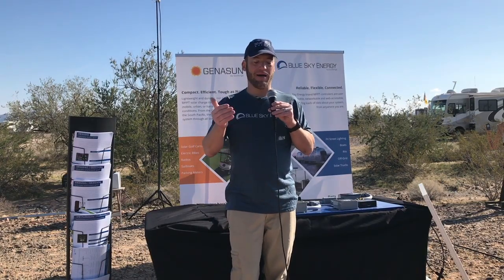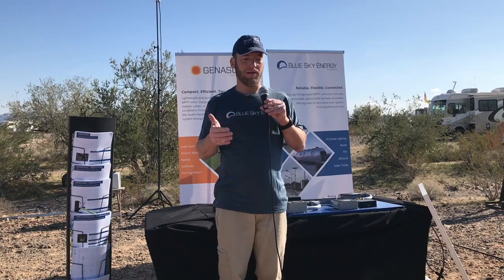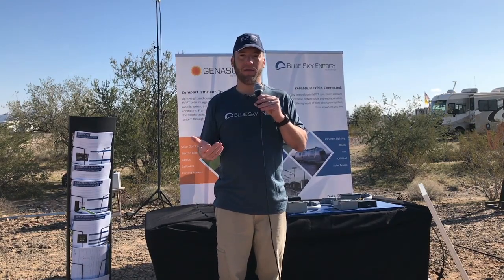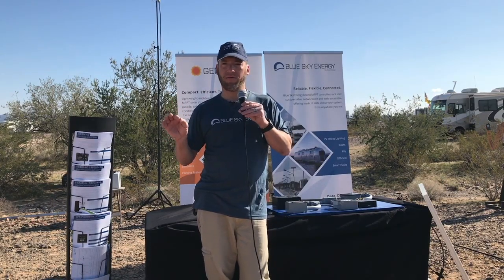The downside of parallel wiring is the size of the copper. When you're working at lower voltages, depending on the distance from your array to your charge controller, you might need bigger wire—more copper—for less resistance.